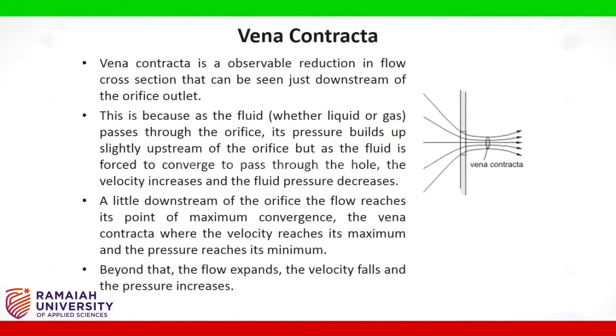Vena contracta is an observable reduction in flow cross section that can be seen just downstream of the orifice outlet. As the fluid, whether liquid or gas, passes through the orifice, its pressure builds up slightly upstream. But as the fluid is forced to converge to pass through the hole, the velocity increases and the fluid pressure decreases. A little downstream of the orifice, the flow reaches its point of maximum convergence — the vena contracta — where the velocity reaches its maximum and the pressure reaches its minimum.